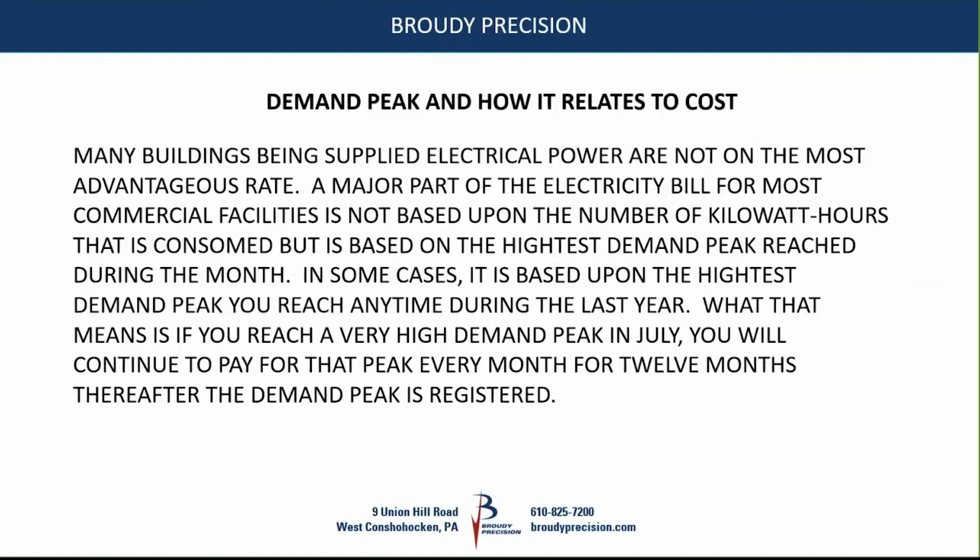Buildings that are being supplied with electrical power are not always at the most advantageous rates. A major part of the electricity bill for commercial facilities is not based upon the number of kilowatt hours consumed, but on the highest demand peak reached during that month.